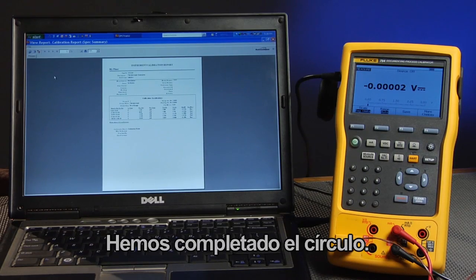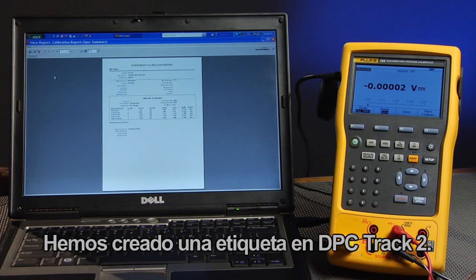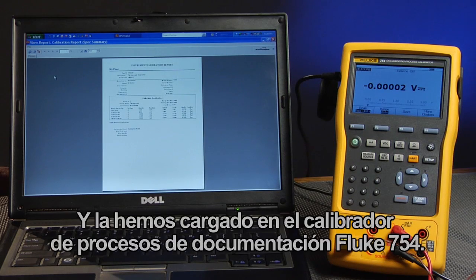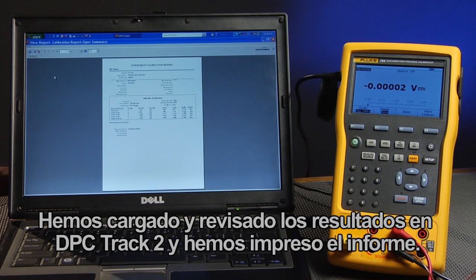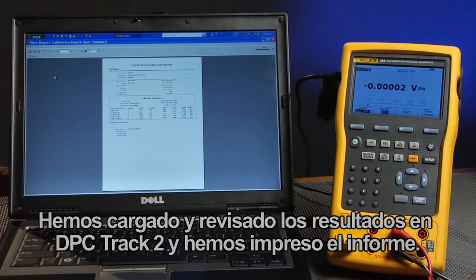We've gone full circle. We've created a tag in DPC Track 2 software, loaded it into the Fluke 754 documenting process calibrator, documented the transmitter results using the downloaded tag, uploaded the results back to DPC Track 2 software, and reviewed the results and printed a report.